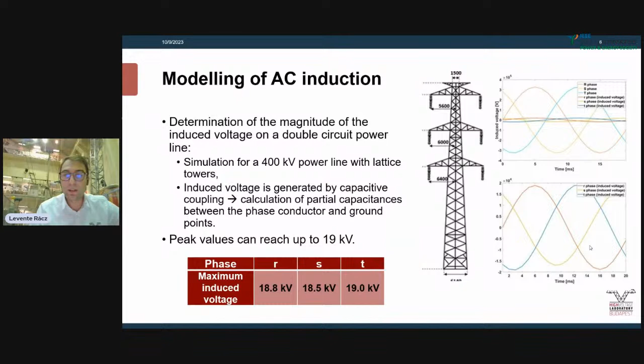For live working, we use conductive suits, and these kinds of conductive suits were modified a bit so that this kind of PPE can be used also for vicinity work. The principle is that this conductive suit has very low resistance conductive tapes, and it can shunt the current, protecting the worker so they can work also on dead parts of double-circuit power lines. These kinds of suits can shunt 50 amperes for 30 seconds, so there will be no heat, no arc, and no problems inside the clothing.